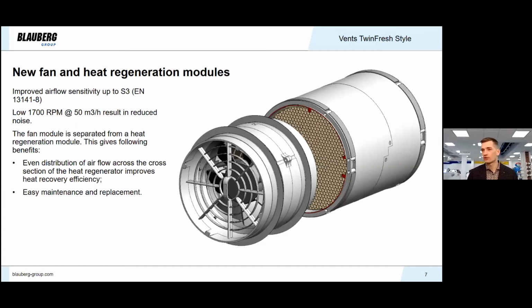And now, new fan and heat regeneration module were developed for the twin fresh style unit. Significant homework was done with new fan module. We have achieved S3 class for airflow sensitivity according to EN 13141-8. Also, we have managed to reach 50 cubic meters of airflow at low 1700 RPMs only, which results in low noise. As you can see, the fan module is separated from heat regeneration module. Yes, this gives following benefits: even distribution of airflow across the cross section of the heat regeneration, improves heat recovery efficiency, easy maintenance and replacement.